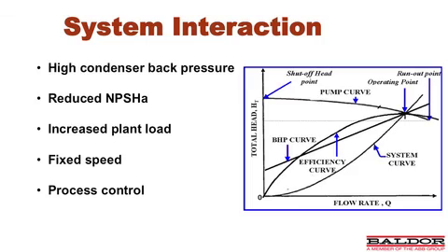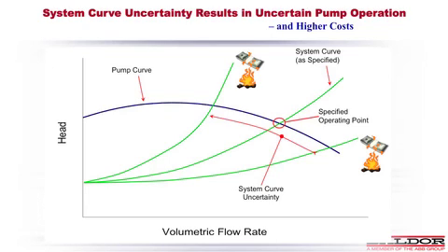Some of the system issues out there are high condenser back pressure. There are situations where you'll have reduced net positive suction head. There's increased plant load. You are committed to a fixed speed application in your current design, and then also process control. All of these issues impact where the pump operating point lies relative to the system curve. System curve uncertainty results in uncertain pump operation, therefore impacting the pump reliability and efficiency.